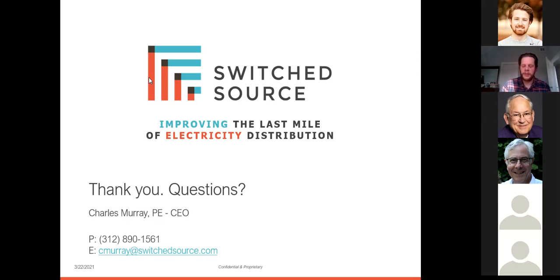The second use case is around solar generation. With solar, there are three real limits utilities care about: voltage limits, and for single phase, balance—high to low voltage balance across the three phases. There are also ANSI requirements around plus or minus 5% voltage they have to give customers from a power quality perspective, which is usually the first threshold you hit. Beyond that, you hit limitations in the conductors and their thermal, current-carrying capability.